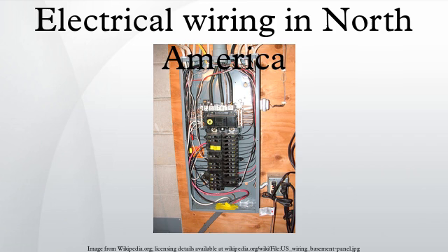Electrical wiring in North America follows regulations and standards for installation of building wiring. Terminology: although much of the electrician's field terminology matches that of the electrical codes, usages can vary. Neutral wire is the return conductor of a circuit. In building wiring systems, the neutral wire is connected to earth-ground at least at one point. North American standards state that the neutral is neither switched nor fused except in very narrowly defined circumstances.